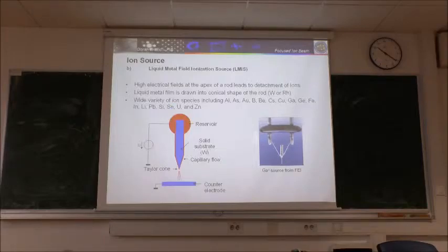And this is the basic idea of the source. You have a very sharp tip. At the end, it's the so-called Taylor cone, physicists would maybe know better. And at the end, you apply a high voltage, in the range of 1 to 10 kilovolts. And those atoms at the top of this cone are ionized. They lose electrons, they become gallium plus, and you just accelerate those ions down the column. And this is a practical ion source from FEI. The lifetime of such an ion source is somewhere around 1,000 to 1,200 hours. So if you use this machine extensively, it should be changed once to twice per year.